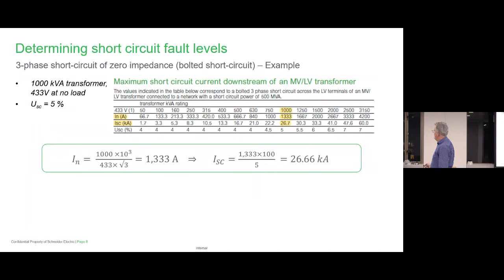The nominal rating of current that can get out of it is 30. Well, I know it's about more 1400 amps. Typically you get about 1400 amps on it, you might get more. The fault level, you'll know off the top of your head, is typically 27 kA. You get a couple of 1 MVAs together, you've got 55 kA.